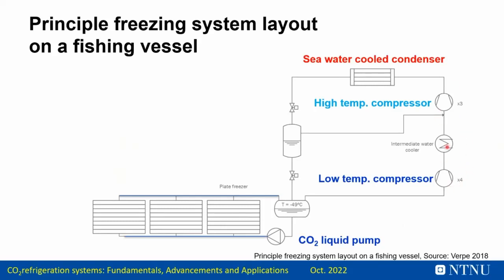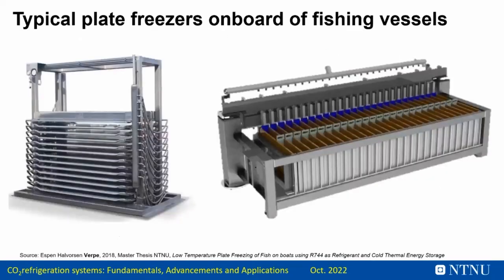You have the two-stage compression, an intermediate water cooler, a seawater cooled condenser, the intermediate pressure vessel and the low temperature pressure vessel at around -50, and the CO2 liquid pump, which delivers the CO2 to all the plate freezers. They look typically like this, where fish is stored between the plates and frozen, and the vertical ones look like this.